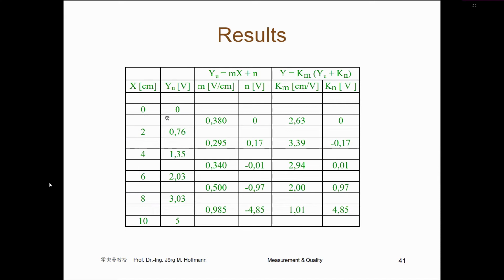You have here the points, that is the uncorrected value, and that is the true value. And the true value is 0, 2, 4, 6, 8, 10 centimeter. And here you have the voltage, what the computer has to read in for these points. And now you calculate at first the m, the amplification, the sensitivity, the multiplicative constant. Everything is the same between these 2 points. And that you can look here, delta y divided by delta x.